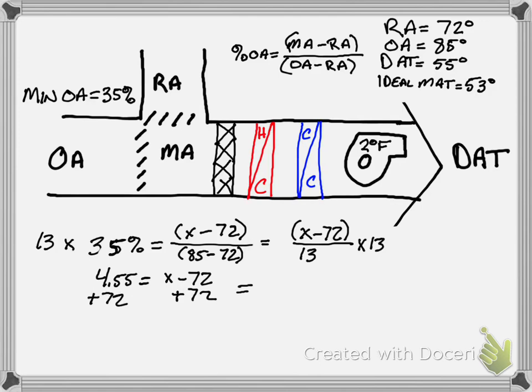And we come up with X or MAT is equal to 76.55 degrees Fahrenheit. And so we know at this scenario that we're going to have to have our cooling coil engaged to reduce the temperature to remove heat from the air handler to get from 76.55 degrees down to 55 degrees. And in a later video we'll show how that heat is removed.